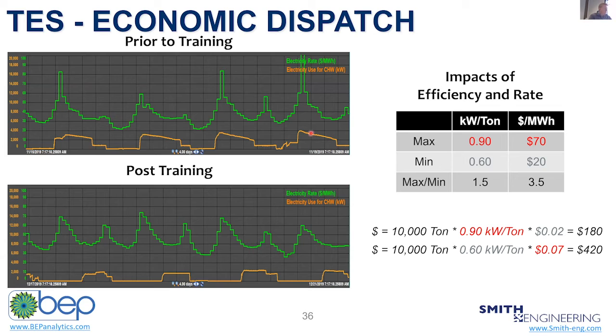So here's UC Davis. They have a very complex rate structure. They get WAPA power, which adds complexity on top of their CAISO. Just to take a step back, if we're not using real rate data, we've got to get there. I think the days of blend rates are over. We've got to really be rate sensitive. And this example points out the rate sensitivity, right? An inefficient plant is running at 0.9 kW per ton, and a really efficient plant is running at 0.6. You can see that the 0.9 at super cheap electric is 180 bucks, and the 0.6 at expensive electric is $420. So at UC Davis, my rate is driving things way more than my efficiency is. So we really have to be rate sensitive, right?